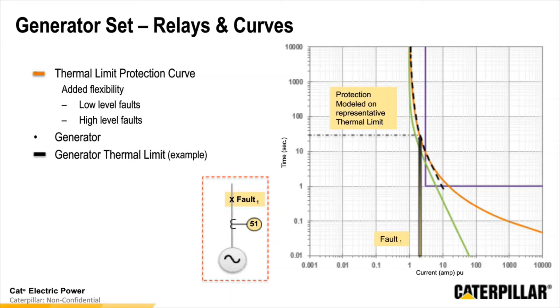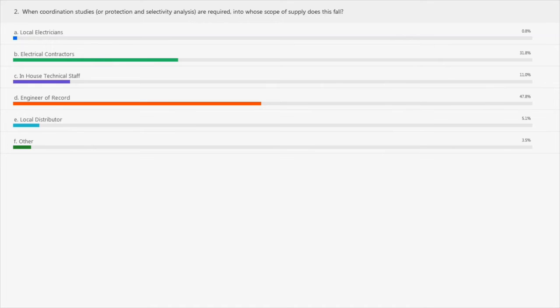So as you can see here with this curve, we've now overlaid the generator thermal limit as part of the overall curve. So we have the thermal limit protection curve, where we can see that instead of the 10 seconds that we had previously, we are now getting up to almost 30 seconds of additional energy. And the generator thermal limit, we can see that we are right on top of that thermal limit. So now we know that we're going to be up to what the capability of the unit is, and we're getting more energy that we need to be able to support those downstream loads or to clear these faults that we have within the system. It'll aid as we go forward and talk about how we coordinate this with all the other breakers in the system at the end. Now let's go to our results for that poll question.